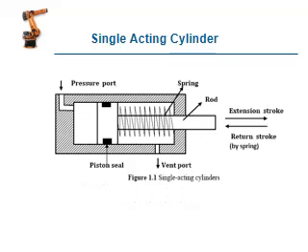This is the rotary actuator. Next is the single acting actuator or cylinder. Inside this cylinder the piston is moved, creating reciprocating motion like extension stroke and return stroke. This figure shows the cylinder with the piston attachment and the seals. On the left side is the pressure port. Oil enters this port, so the piston moves to the right side. I think this is the extension stroke.